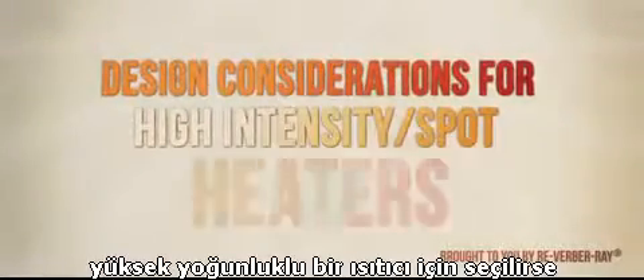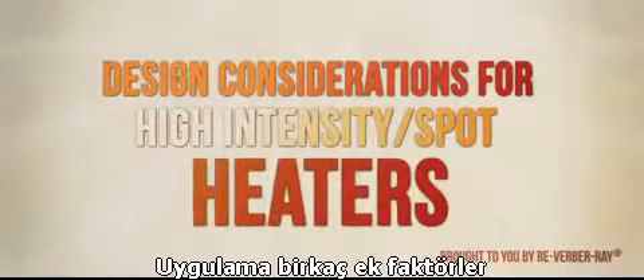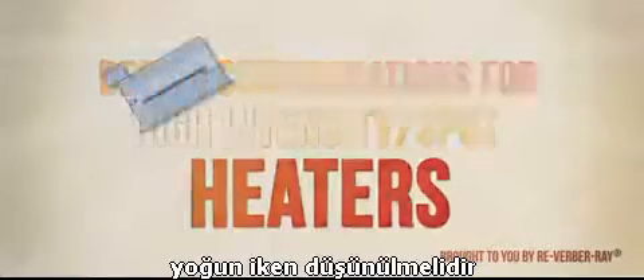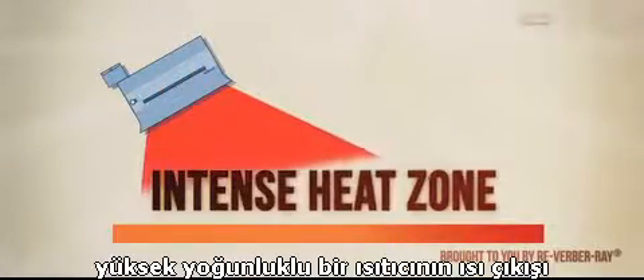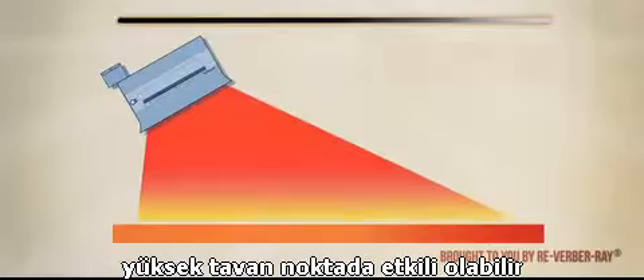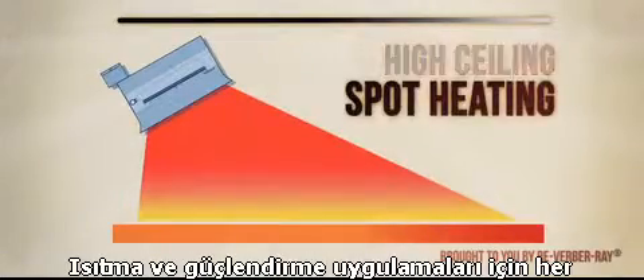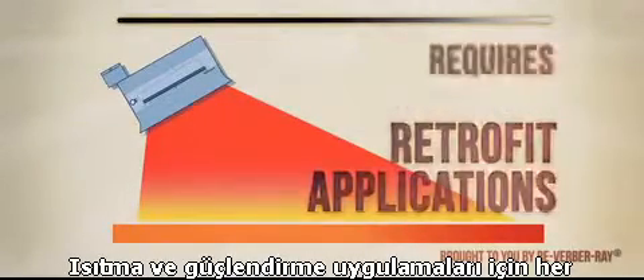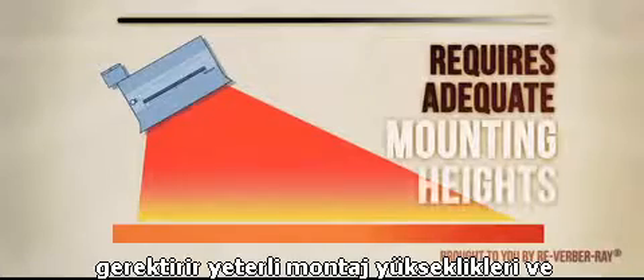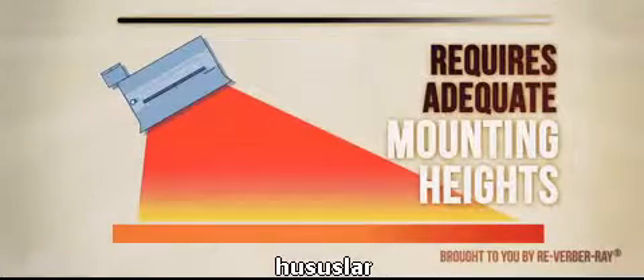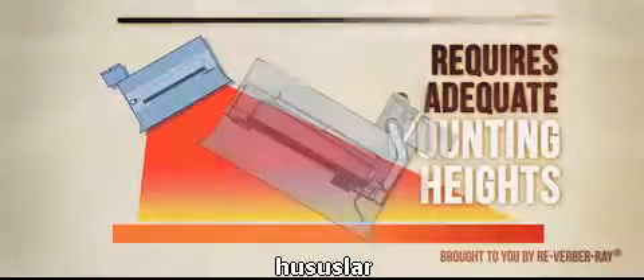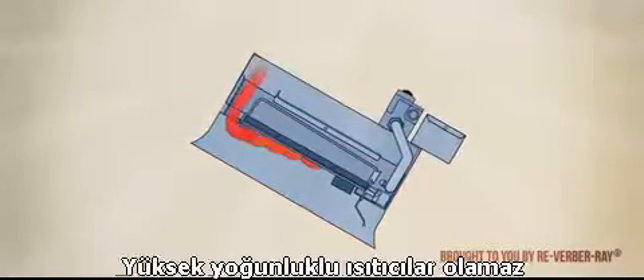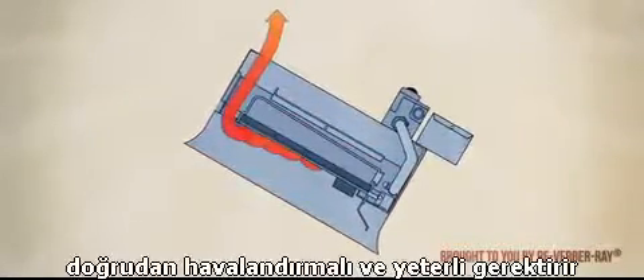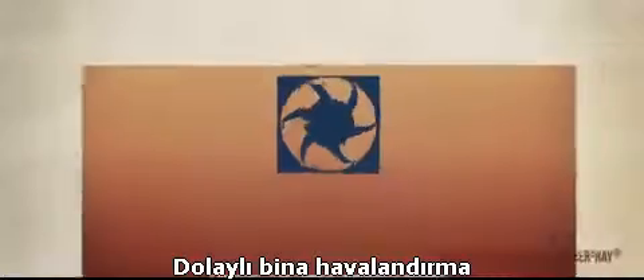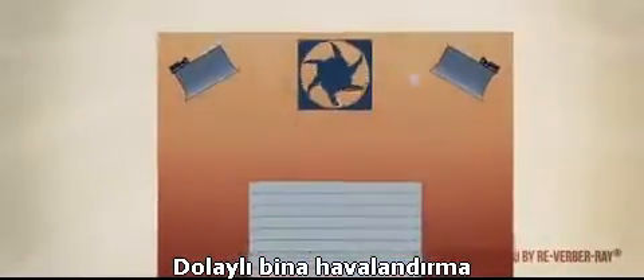If a high-intensity heater is chosen for the application, a few additional factors should be considered. While the intense heat output of a high-intensity heater may be effective in high-ceiling, spot heating, and retrofit applications, it requires adequate mounting heights and increases the clearance to combustibles considerations. As a direct fired appliance, high-intensity heaters cannot be directly vented and require adequate indirect building ventilation.